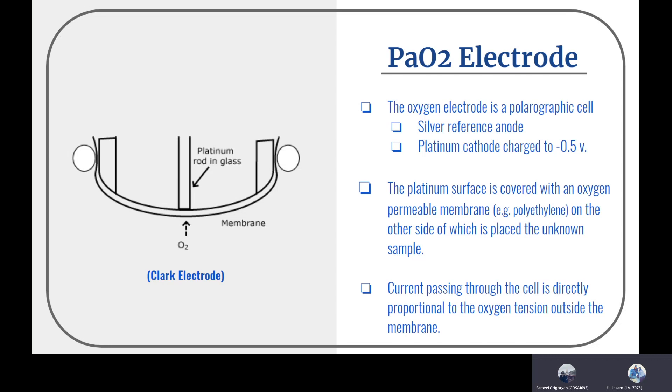The current passing through the cell is directly proportional to the oxygen tension outside the membrane, so it directly measures the oxygen amount. Another name for this one is the Clark electrode, named after the scientist that came up with that sensor.